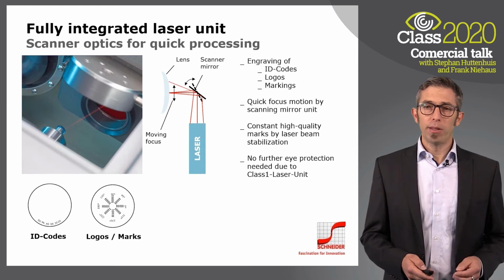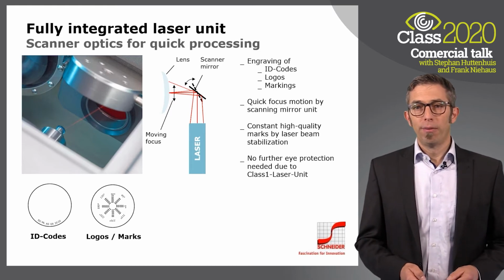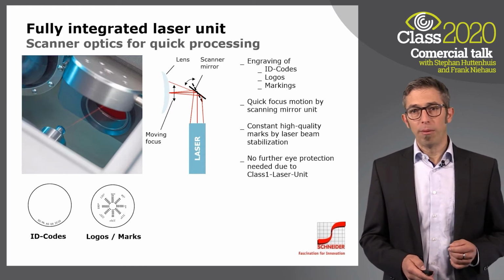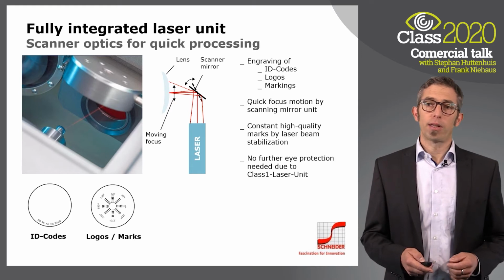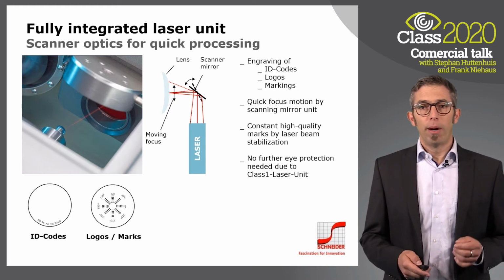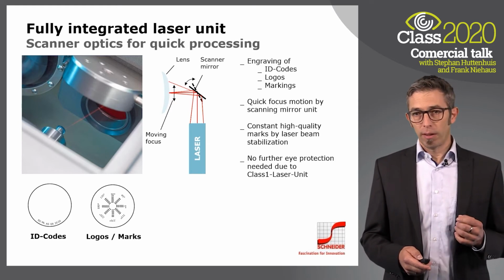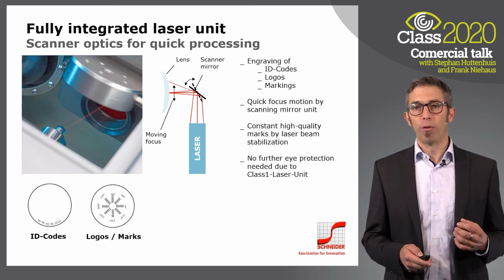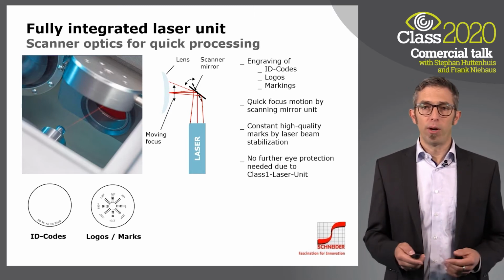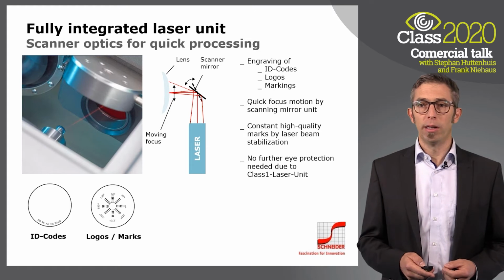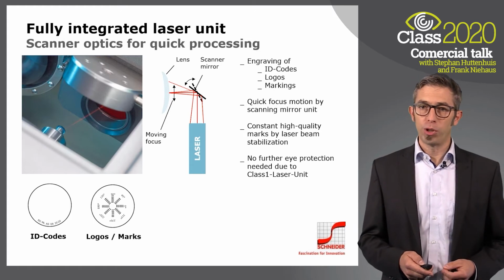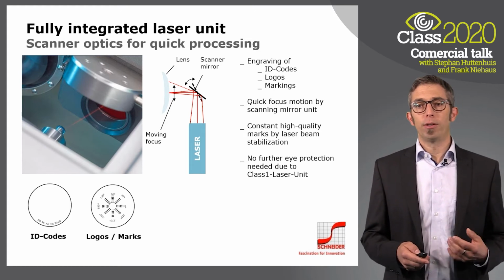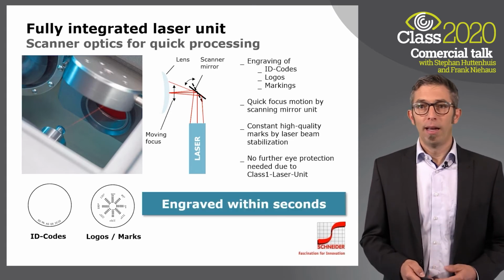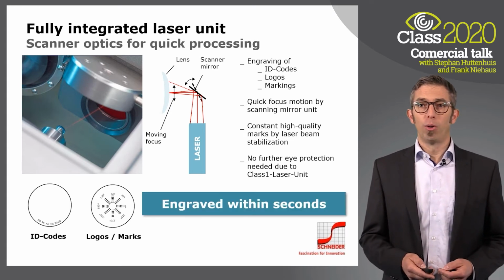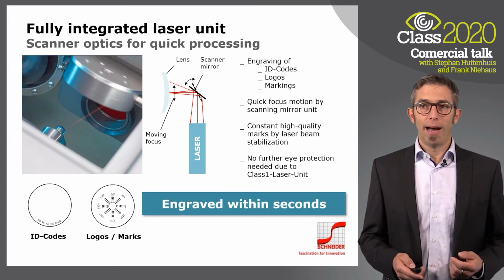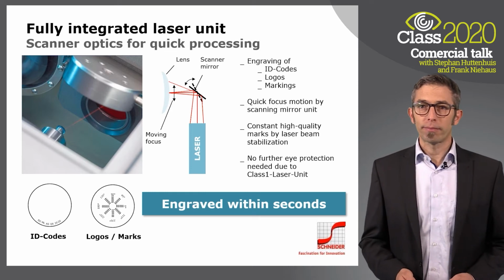But the real specialty of this laser is that it's using a scanning mirror, as you can see in the sketch beside the picture. By the moving mirror, the laser focus is moving over the lens surface. This avoids time-consuming repositioning of the lens with the machine axis for every dot in the marking. Hence, even larger ID codes or special engravings are done within seconds.